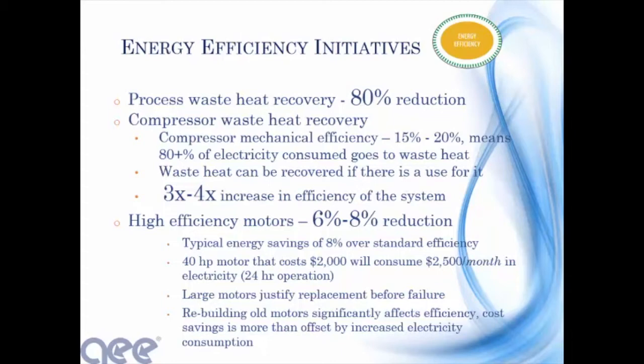Another note about motors is it's a fairly common practice for big motors to rebuild them if they fail. When you do that, they can lose a few percent efficiency, and it still costs money to rebuild that motor. It may cost half as much as a new motor. So we have stopped the practice of rebuilding old motors. If a motor fails, we're going to replace it with that NEMA Premium or Super Premium model and go for the efficiency. It'll more than make up for it over the life of that motor.